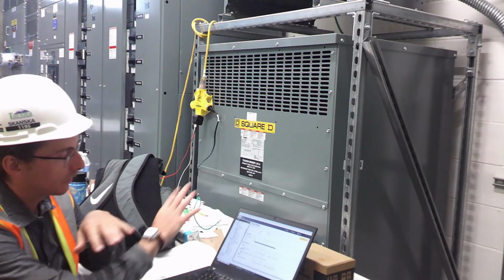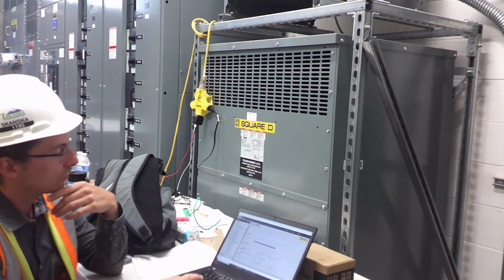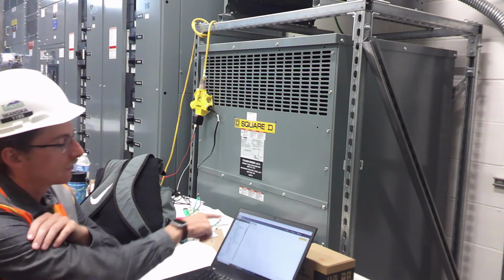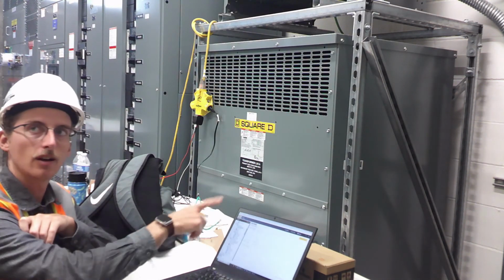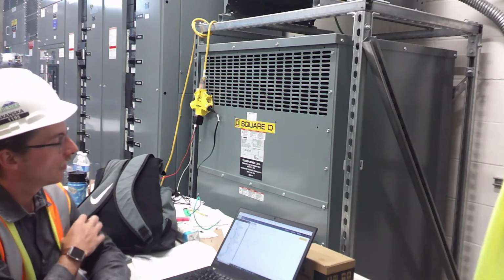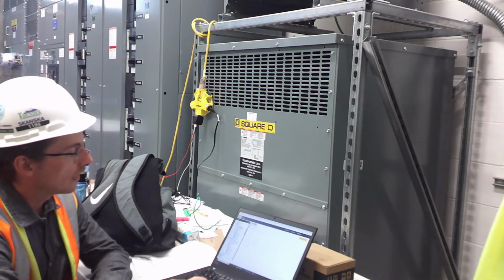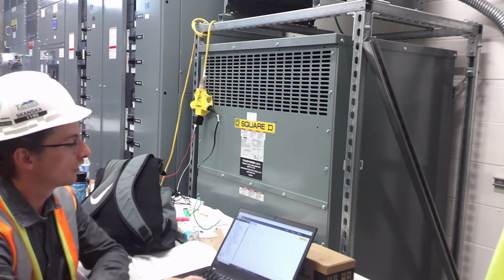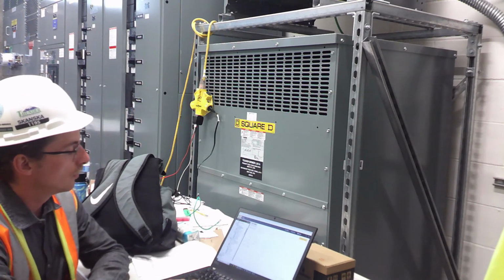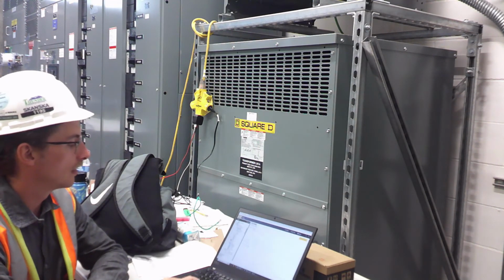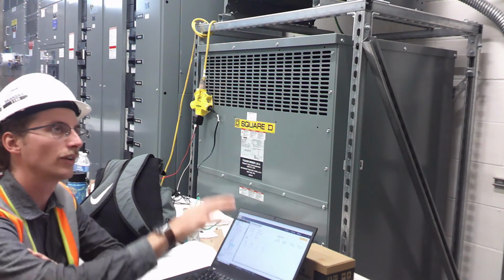Quick thing just about this in general, you have these bridges here. When you click on them, there's an example. This bridge is not talking back to the area controller right now. It's because I have the cables unplugged. So that'll highlight red if it can't actually talk to the device. That's just a good thing to know. If you come in here and click these and it's not actually talking to them, and then you try and save the schedule, it's not actually going to reach the device.